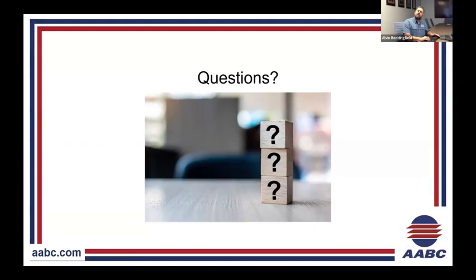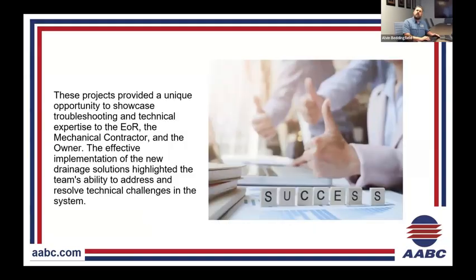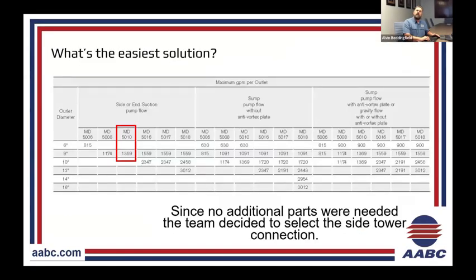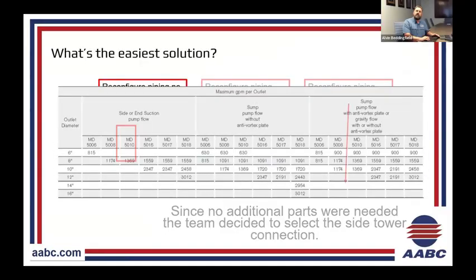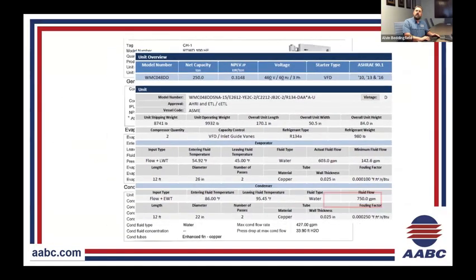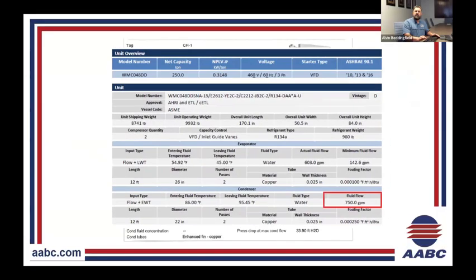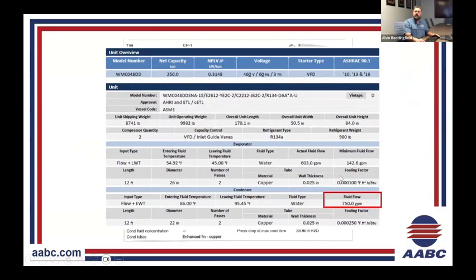So the person says, was the flow rate meant to be condenser side, not evaporator side? No. The flow rates were designed on the condensing water side, because right here on both chillers, this is going to be your condensing water flow, and this will be our actual flow for the evaporator side. So both towers were designed for the condensing water flow.